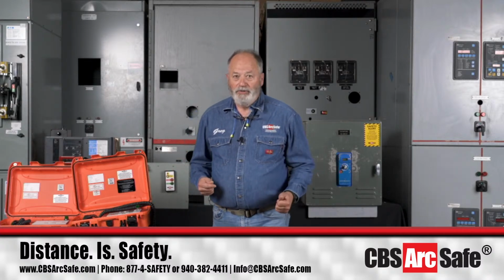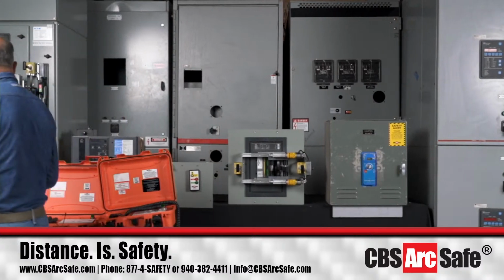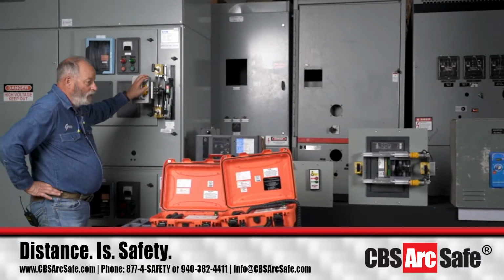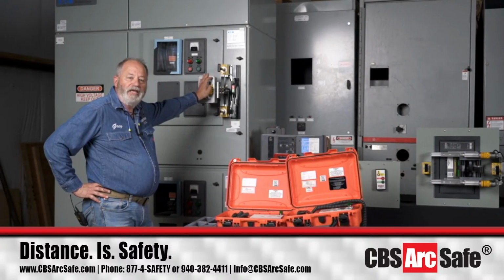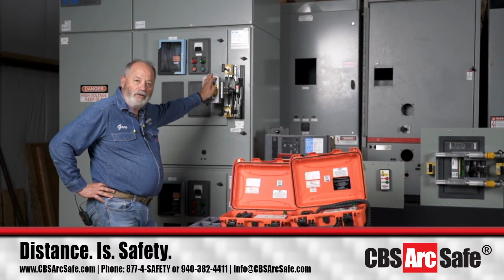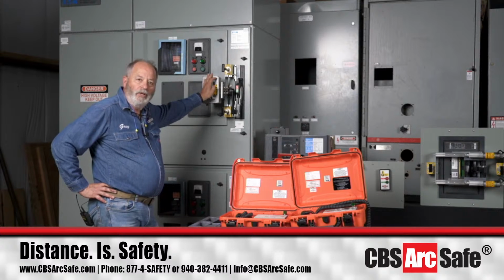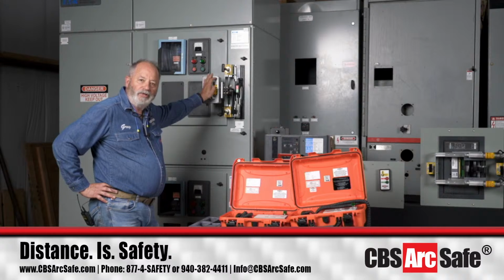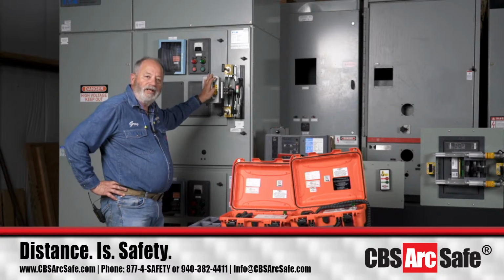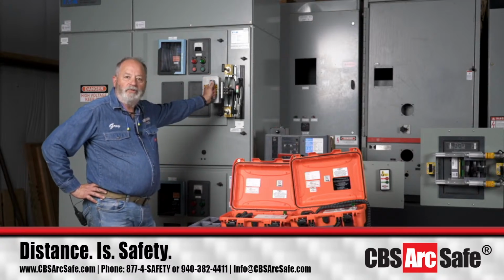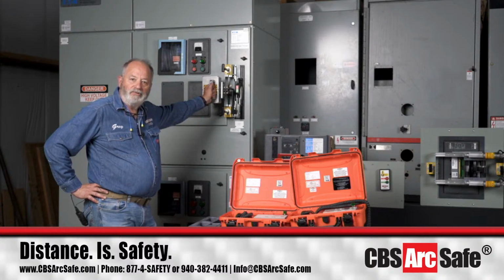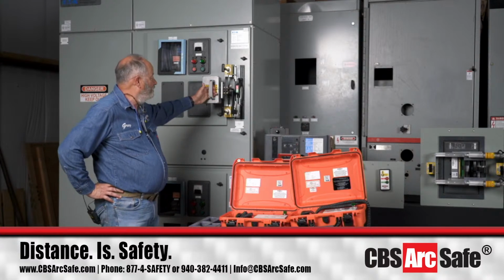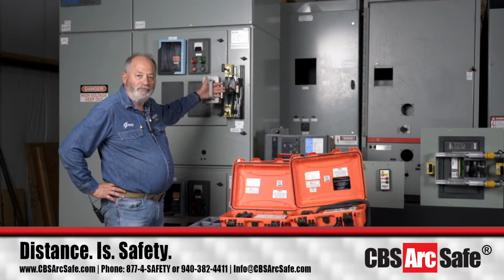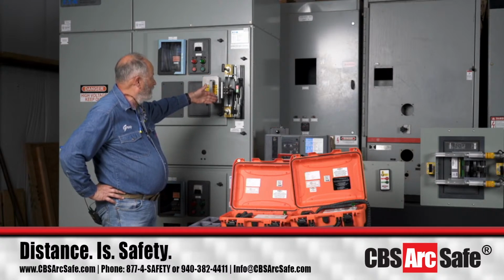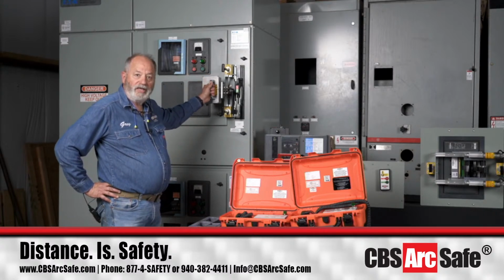The first product we're going to start with today is our RSA 10A. The original Amp Guard was a 1958 version made by Westinghouse, and we've seen very few of those. Those look like an old Westinghouse 11300 series long size 5 motor starter. From 1958 to 2004 is what we'd call the classic Westinghouse Amp Guard. In 2004, after the acquisition by Eaton Cutler Hammer of Westinghouse, Eaton came up with this design, which we'd call the current vintage of Amp Guard motor starters.